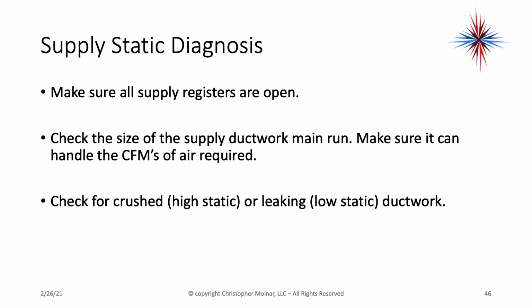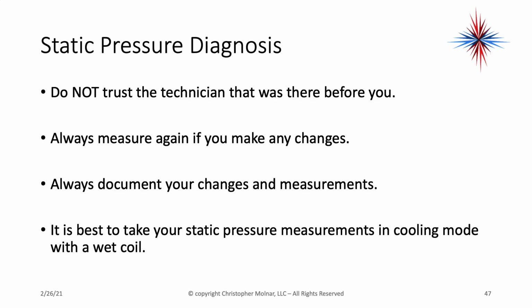Make sure all the supply registers are open. Check the size of the supply ductwork main run. Make sure it can handle the CFMs of air required. Check for crushed, high static, or leaking, low static ductwork. Do not trust the technician that was there before you. Always measure again if you make any changes. Always document your changes and measurements. The best way to take your static pressure measurements is in cooling mode with a wet coil.